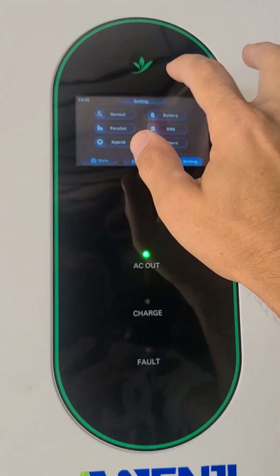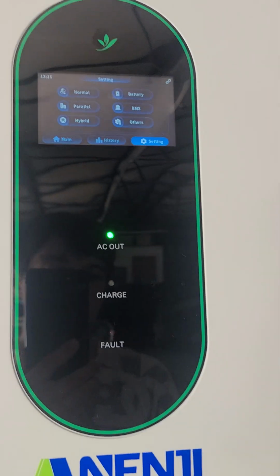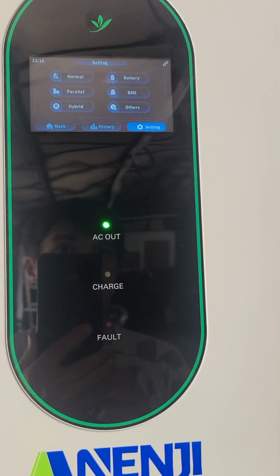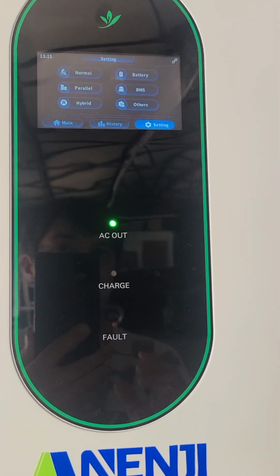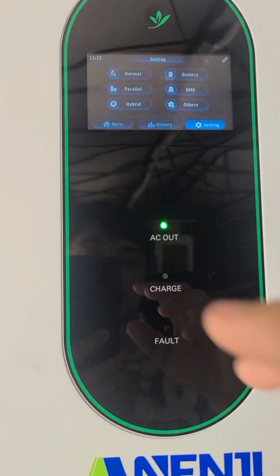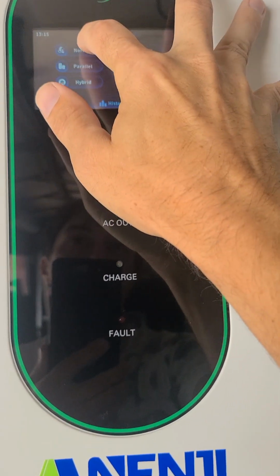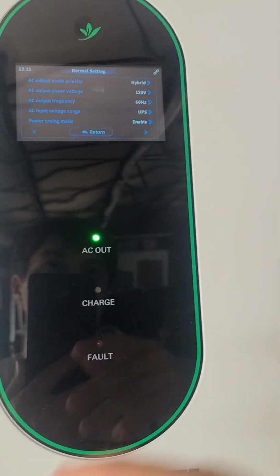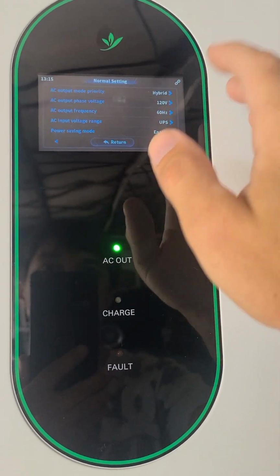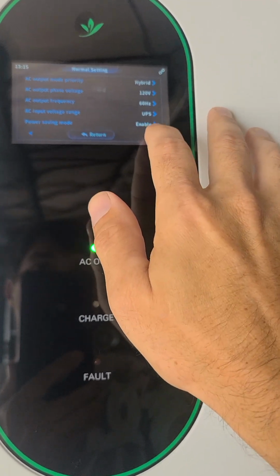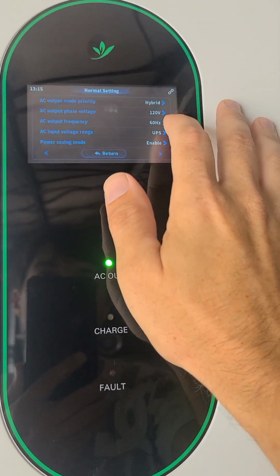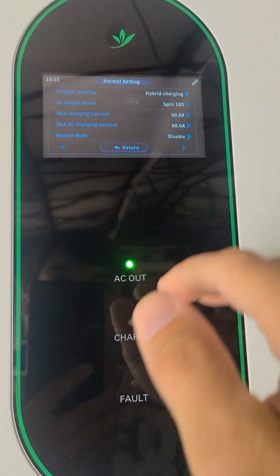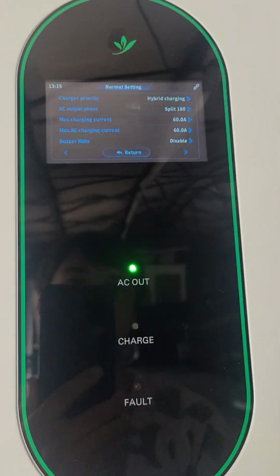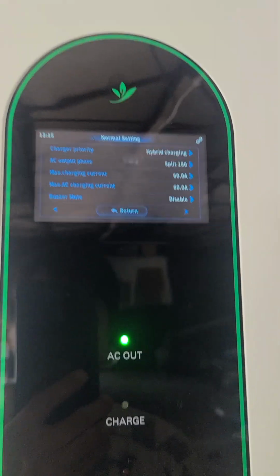And I'm going to show you how to set all this so that it works with zero export. And I'm going to explain it to you, describing it as I go through the settings in a way that you will understand. So here our AC output mode priority is hybrid. That's how we get into hybrid mode. Our output phase and all this just stays default. I have turned on power saving mode, but 120 volts, 60 hertz UPS, that's standard. Our charge priority is forced into hybrid when we're in hybrid mode.